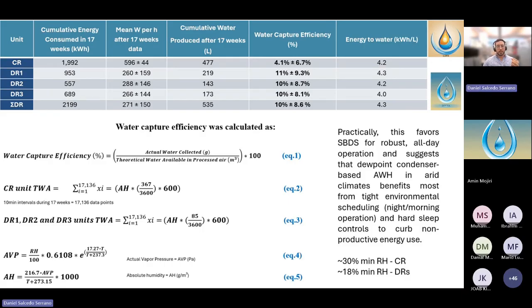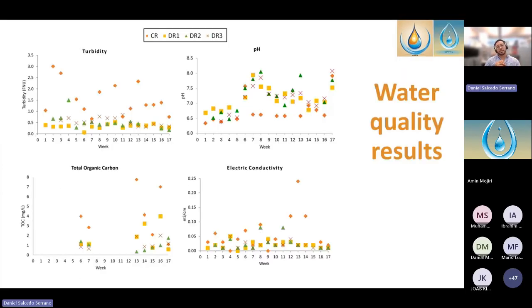And this comes because the compressor would only work when the relative humidity was higher than 30%. And if you remember the last graphic, that was not the case most of the time. And the sorbent-based units will capture water at humidity as low as 18%. I think that's one key thing. Now let's go to water quality.